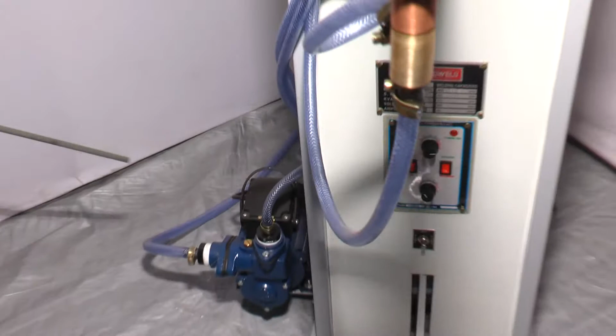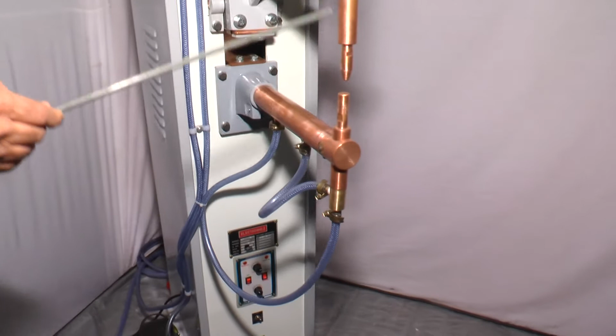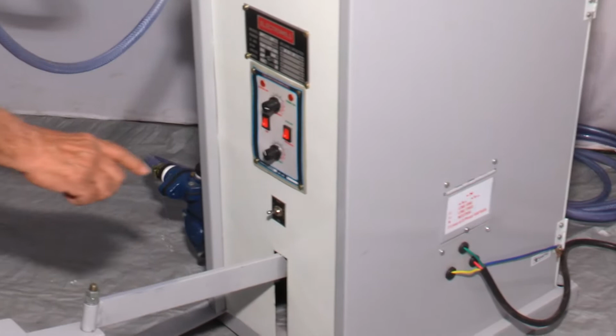This one over here is the water circulating pump that cools the secondary from here to here, again from here to here, so that while welding you get the consistent current all the time. This machine needs to be connected to two lines of 3-phase 415 volts 50 HZ 40 ampere power supply. So with this grooves, the chart is given over here how to connect the cable, that also is mentioned over here. This over here is a pump on-off switch for circulating the water.